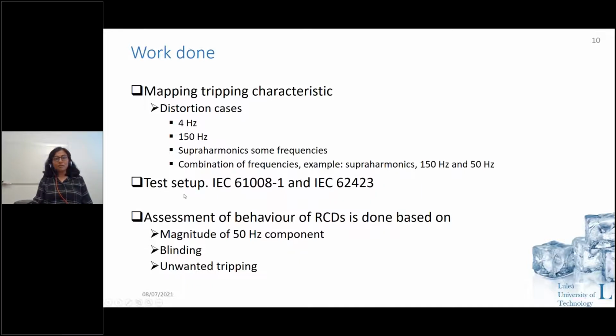Then we used a setup that is defined by IEC 61008-1 and IEC 62423. The first is for type A and AC, and the second is for type B and F. But the test setup is quite similar, because IEC 62423 refers to using the same test setup as 61008-1. And how did we assess the behavior of RCDs? That is based on the magnitude of the 50 Hertz component in the tripping current, and whether, according to that magnitude, the RCD is blinding or it is an unwanted tripping.